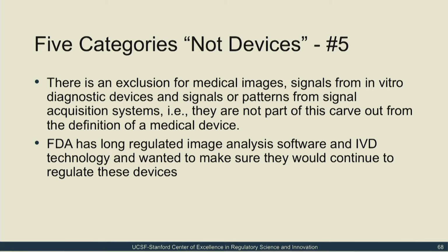However, it's not surprising. Had this clause not been included, one could argue that computer-assisted detection or diagnostic devices that analyze image data, for example, identifying suspicious lesions in MRI scans, and in vitro diagnostic devices are a type of clinical decision support. Yet, for decades, FDA has regulated software that analyzes medical images and certain signals from electronic medical devices, as well as software that processes signals from in vitro diagnostic devices. So this clause simply signifies that the agency intends to continue to do so.